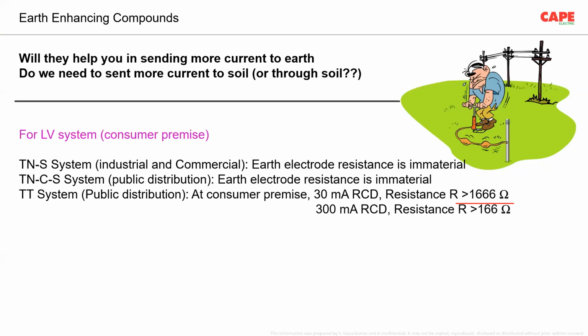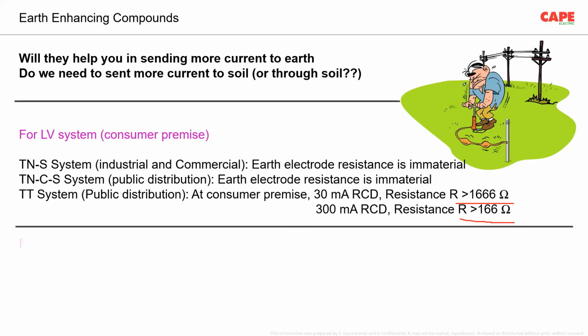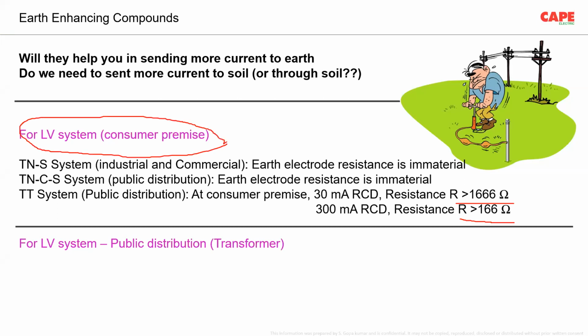If you use a 300 milliampere RCD in a TT system, then the earth electrode resistance is 166. Of course, these values are a little bit higher. Probably it is not the earth electrode resistance, it is actually the impedance of the entire loop. Now for low voltage public distribution, for the utility company, the first one for LV system, this is applicable for a consumer premise if you are a user of electricity, whereas this one is applicable for the electricity supply company.